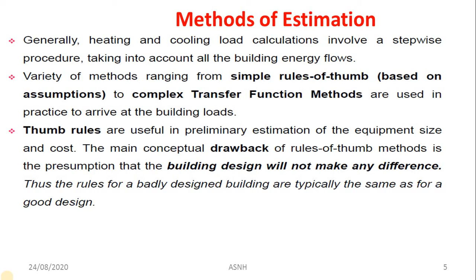Consider the example of an office building. In case of an external zone, if we use 25% glass, 50% glass or 75% glass, then the tonnage capacity is 3.5 TR, 4.5 TR and 5.0 TR. This is according to the thumb rule. But most important, we have to consider an area of 1000 square feet, and only then can we apply this thumb rule. On that basis you can apply a similar thumb rule for others if the area is changed. If the building is in an internal zone, then tonnage capacity is around 2.8 TR.